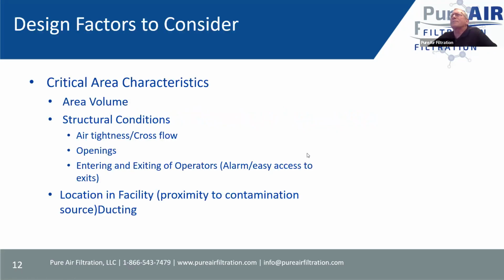Some critical area characteristics. The area volume. Again, that helps us size it. We need to know how large the area is that we're pulling the air from. Structural conditions, air tightness, crossflow. Crossflow is very important when the blower turns on an emergency gas scrubber. It's good to have some crossflow coming through the room. It just helps the piece of equipment pull the toxic gas in.